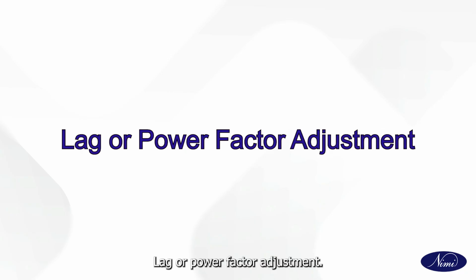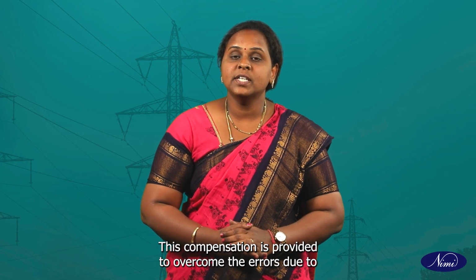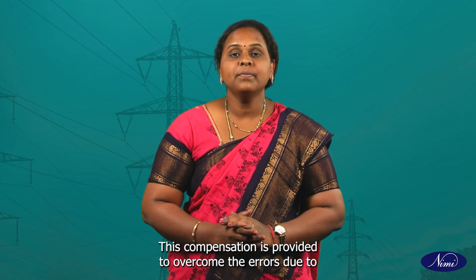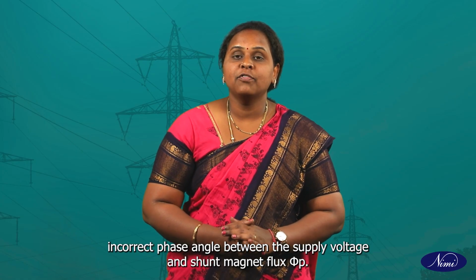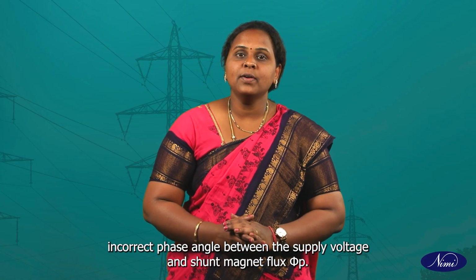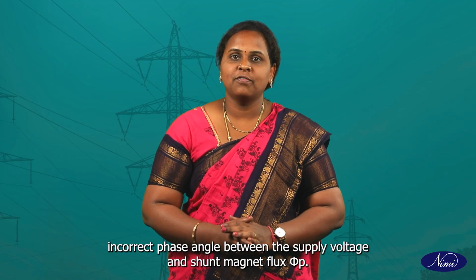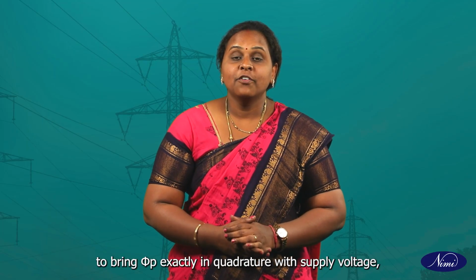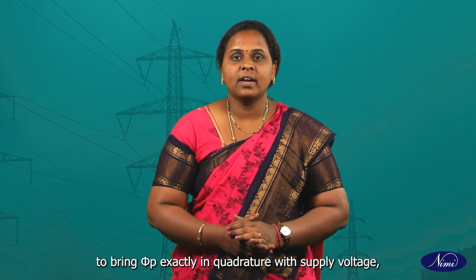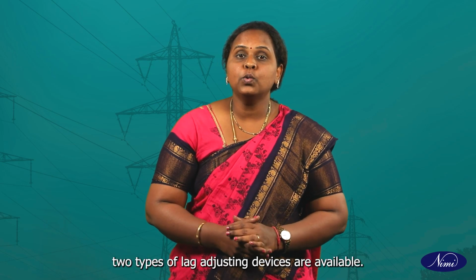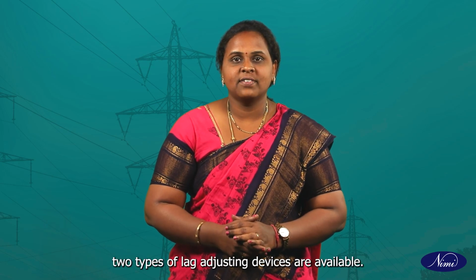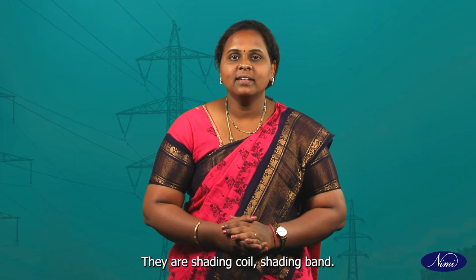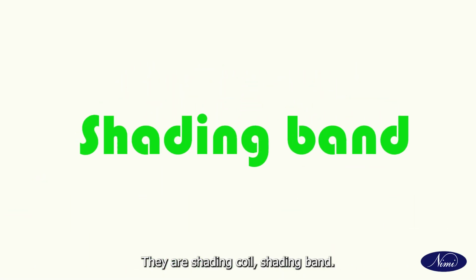Lag or power factor adjustment. This compensation is provided to overcome the errors due to incorrect phase angle between the supply voltage and shunt magnet flux phi p. To bring phi p exactly in quadrature with supply voltage, two types of lag adjusting devices are available. They are shading coil and shading band.